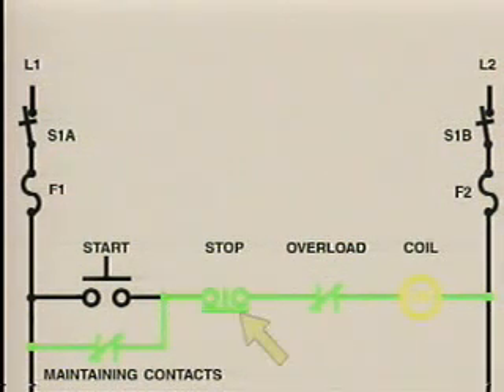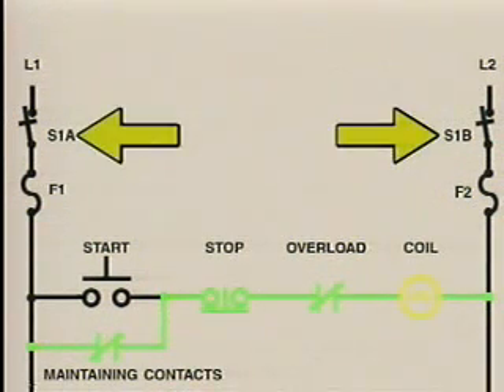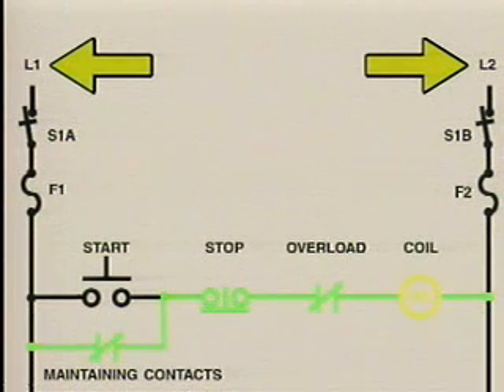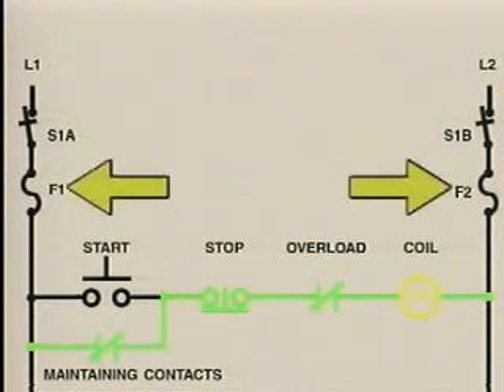Current will continue to flow until its path is opened or the source voltage is removed. The path will be opened if the stop switch is pressed or if the overload contacts open. The path will also be opened if any of the lines connecting the energized components open, or if any of the 4 energized components fail in the open position. The circuit's source voltage can be removed if the power switch is turned off, or if either or both of the phases is lost. Also, if either of the fuses for those phases opens, there will be no current flow through the coil.